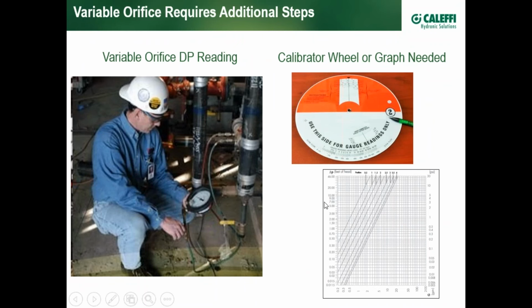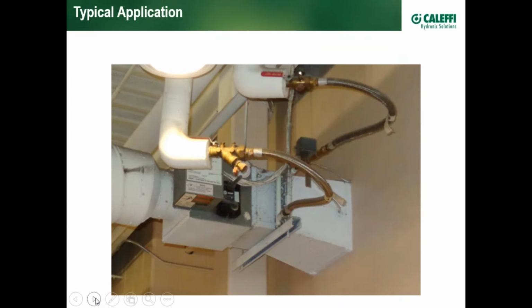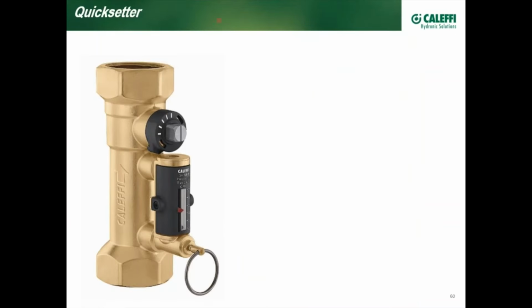And resultingly, tools such as charts like this or calibration wheels like this are used in setting the flow rate. So regardless of variable or fixed, because of what is involved in setting the flow rate, oftentimes you see something like this, where the contractor has placed the valve in the fully open position rather than risk not setting it correctly. And I think I would rather do that, fully open versus fully closed, if I was a contractor not knowing as well.